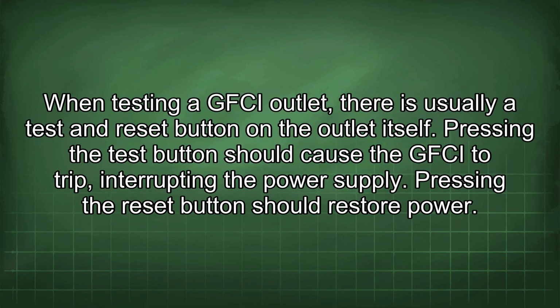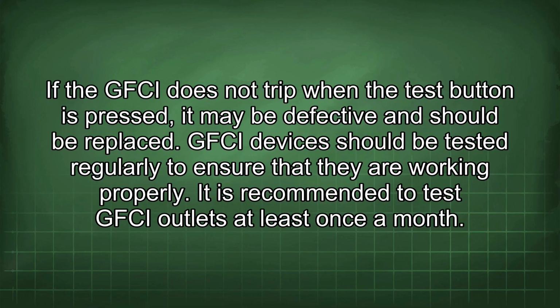When testing a GFCI outlet, there is usually a test and reset button on the outlet itself. Pressing the test button should cause the GFCI to trip, interrupting the power supply. Pressing the reset button should restore power. If the GFCI does not trip when the test button is pressed, it may be defective and should be replaced.